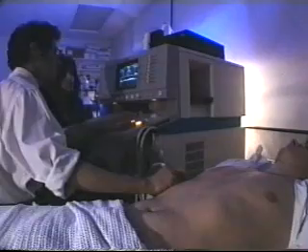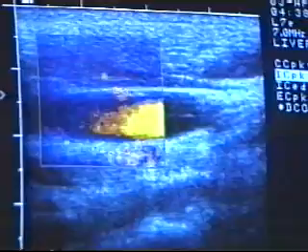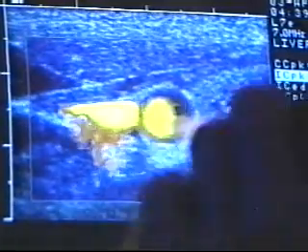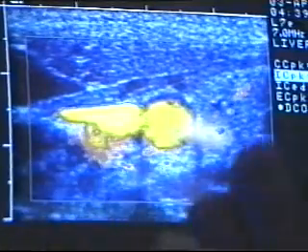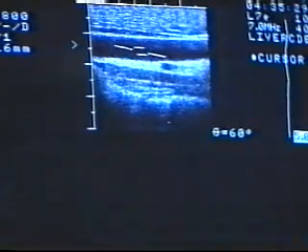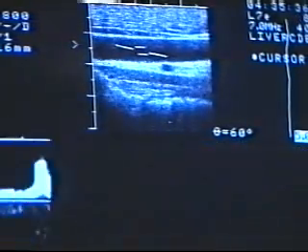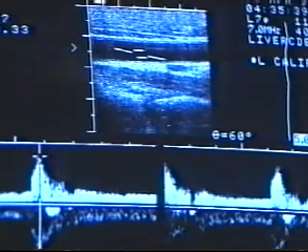Some machines combine Doppler ultrasound with ultrasound imaging to find out how fast the blood is flowing through veins and arteries being studied on the screen. In colour flow mapping, the blood velocity measurements are colour-coded and overlaid on the image of the vessel. You can see the artery — whoosh, whoosh — and the vein is this constant flow. Alternatively, velocity time graphs may be constructed on screen and measurements read off, giving a graphical description of the speed of blood motion. You can freeze it and then do calculations to measure the velocity — 0.78 metres per second of the blood in the carotid artery.